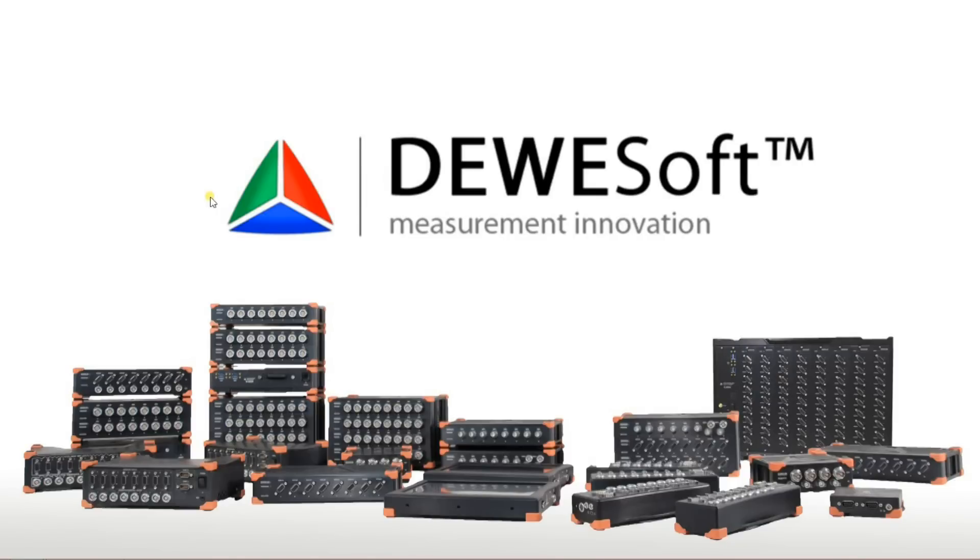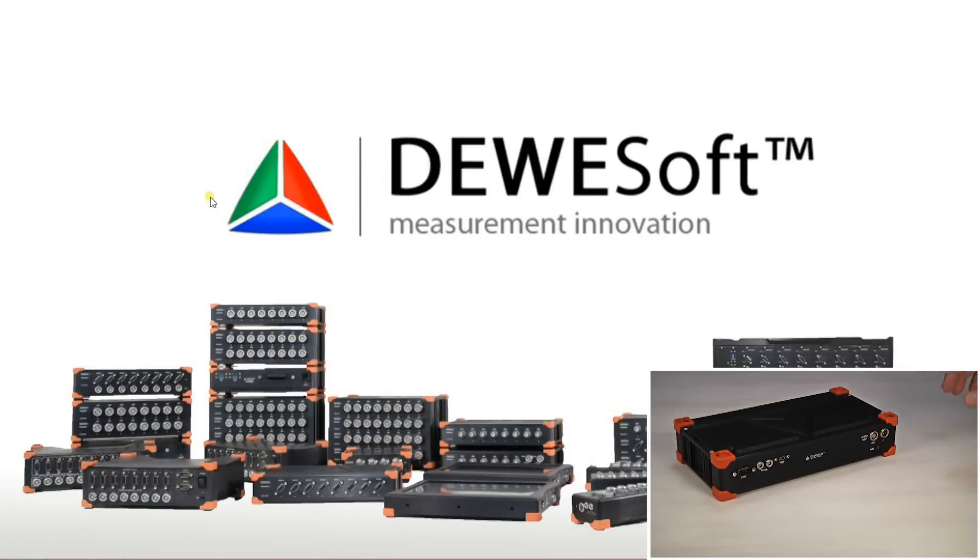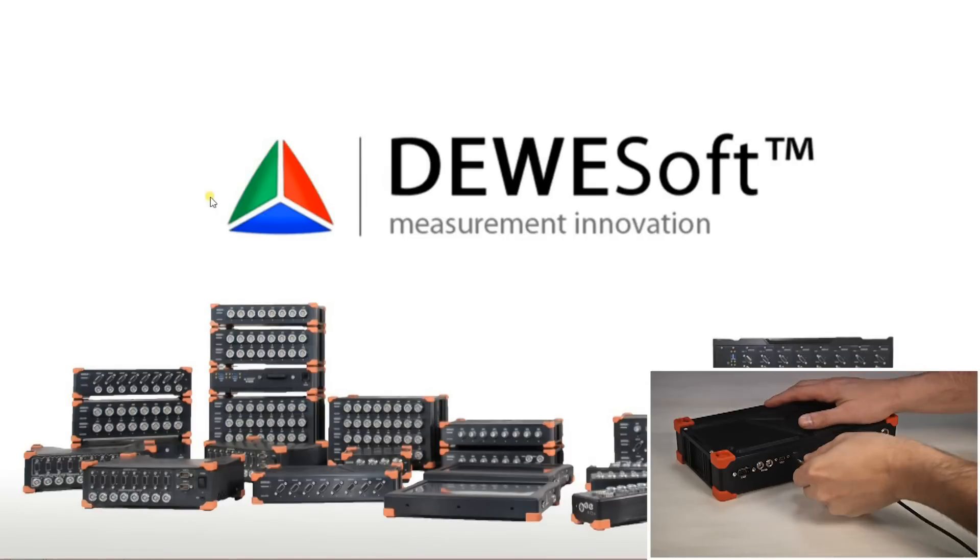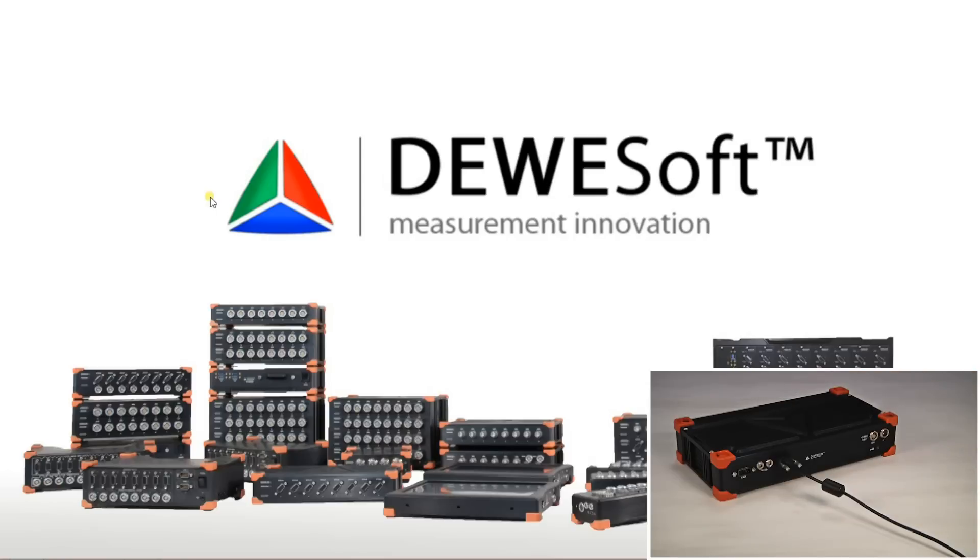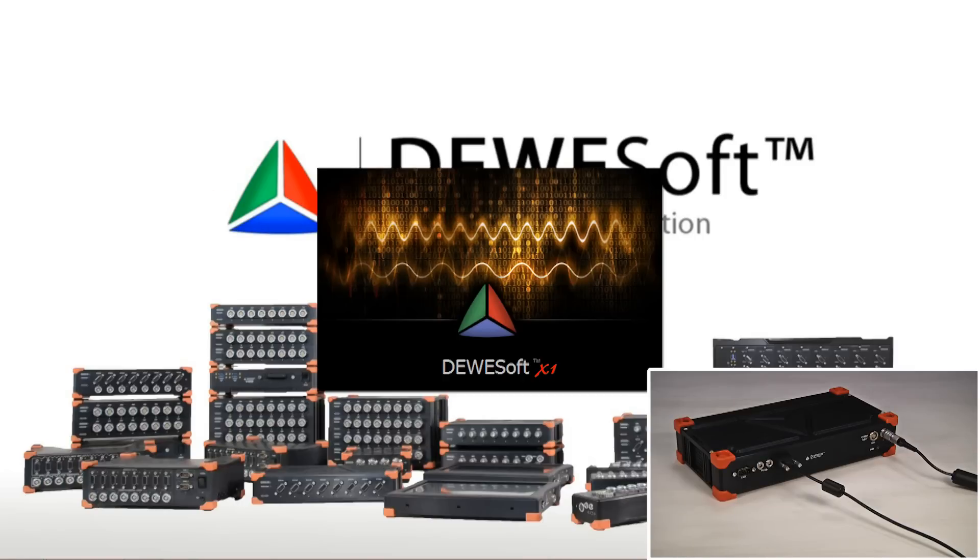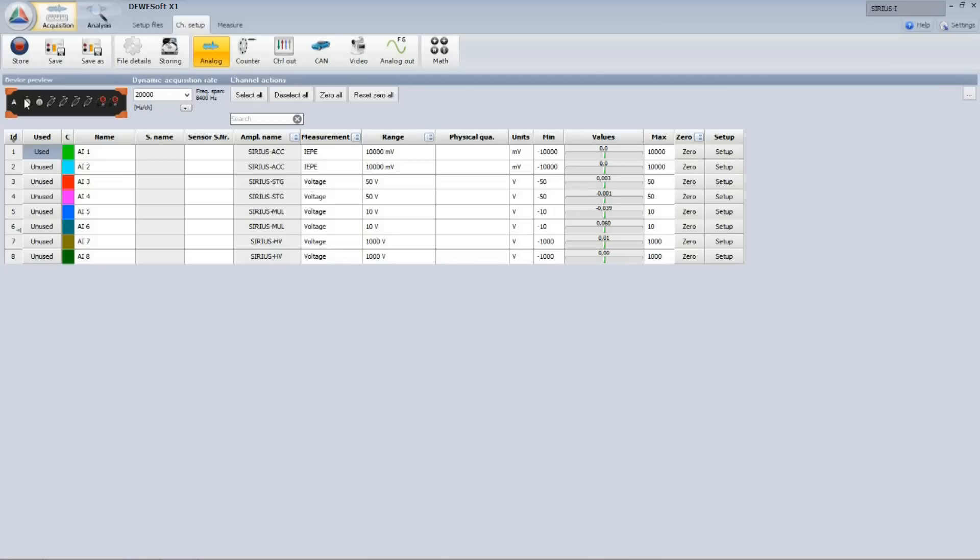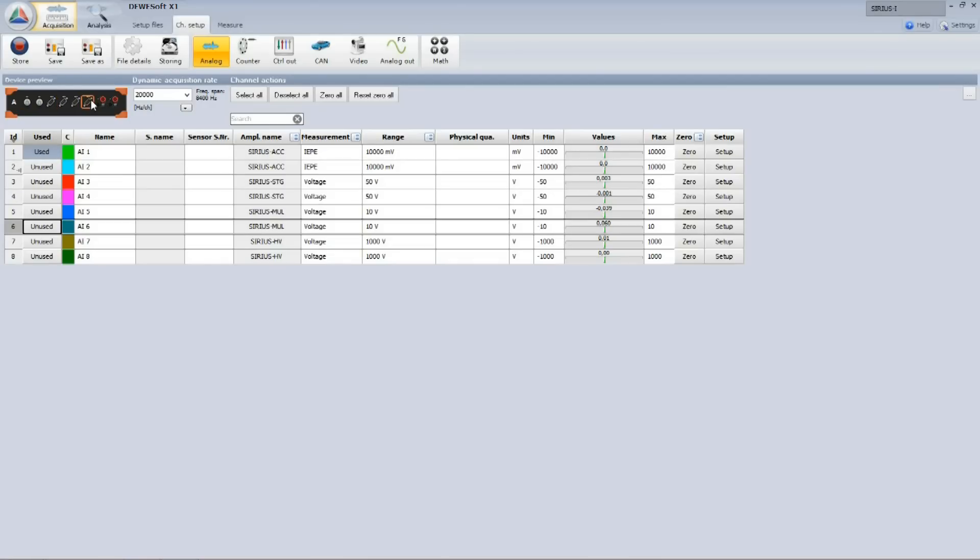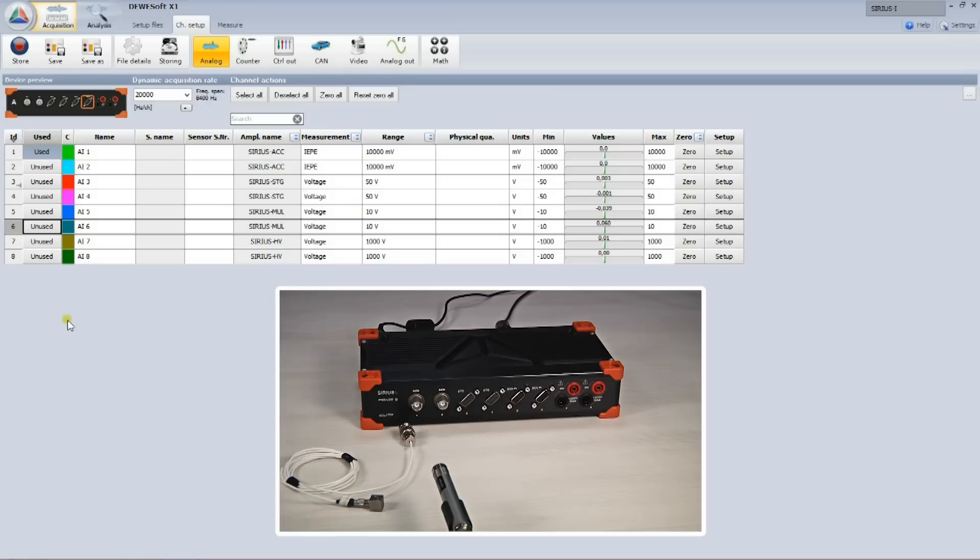Step number one is to connect the instrument and the sensors. As soon as the instrument is connected to the computer, I get a display screen with information that the power is missing. When I connect the power to the SIRIUS instrument, I am ready to run Dewesoft. In Dewesoft, I can see hardware configuration of the instrument and the channel list. Now I can connect my sensors.